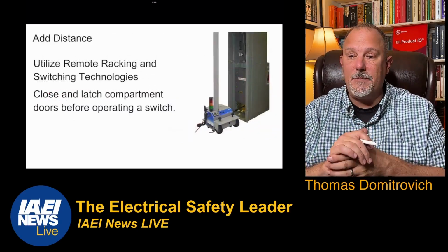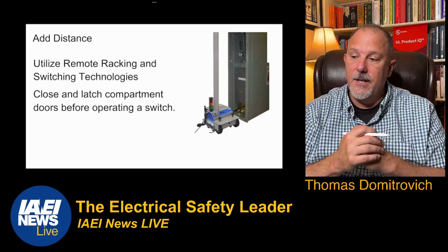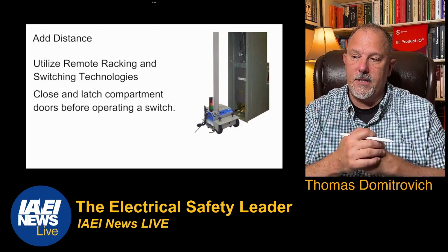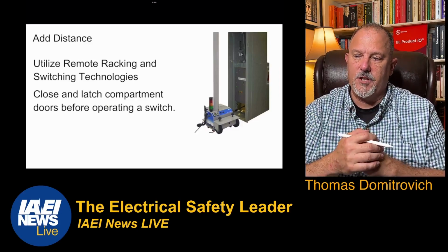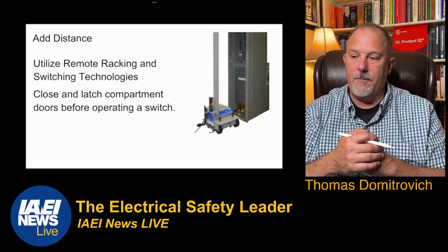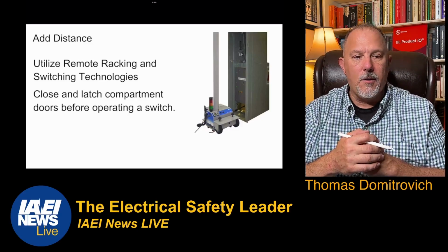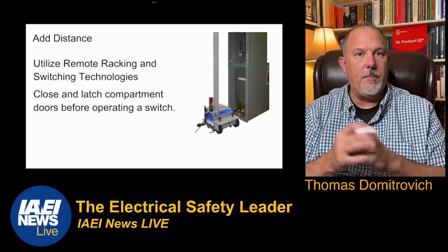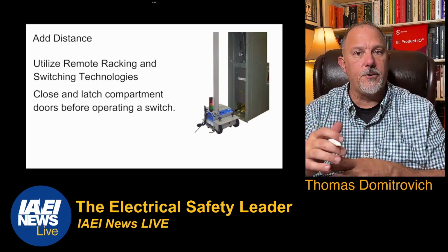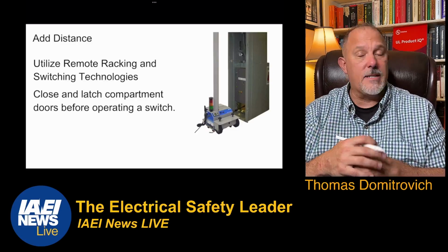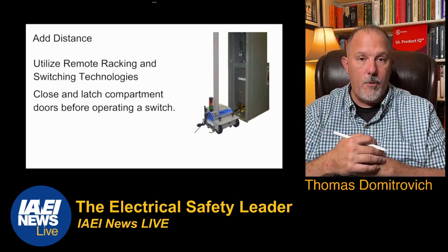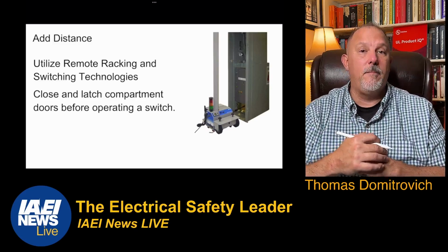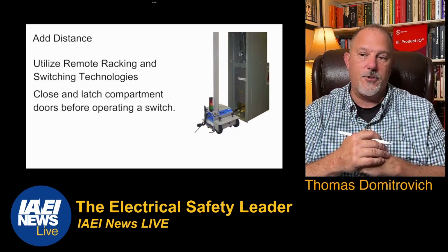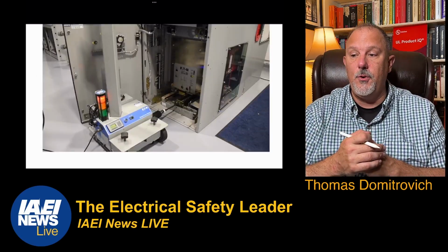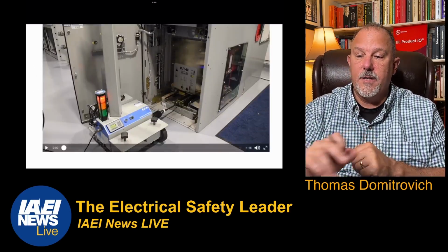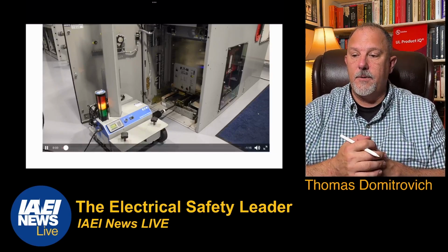Then you have these types of adding distance. These are types of robots. This is a medium voltage breaker that can be racked out from this little robot. There are other types of switches that can be placed on the front of smaller breakers. It doesn't matter. You can get a remote actuator from multiple manufacturers who make solutions to get you away from the center. So here's an example.